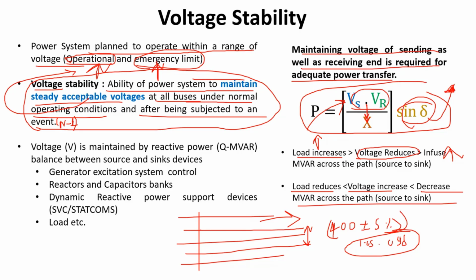And if it goes on increasing, then you already know that your operation follows the swing equation, which is like this, right? So this is P and this is delta. If you are operating here, let us say at sine 15 degree, and the voltage is reducing and you want to transfer the same amount of power, it is going to 30 degree, 40 degree, 45, and then 90 degree. And after that, if you want to transfer any amount of power, it is going to get reduced, meaning active power will reduce. So what will happen? You enter into the state of instability.